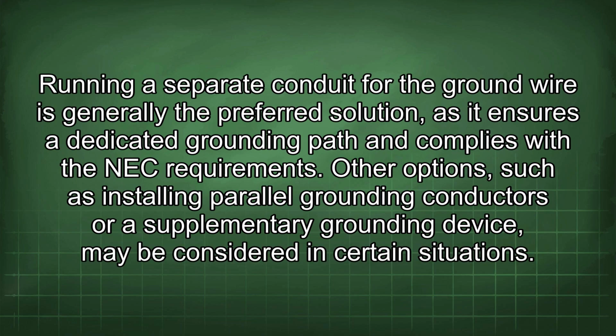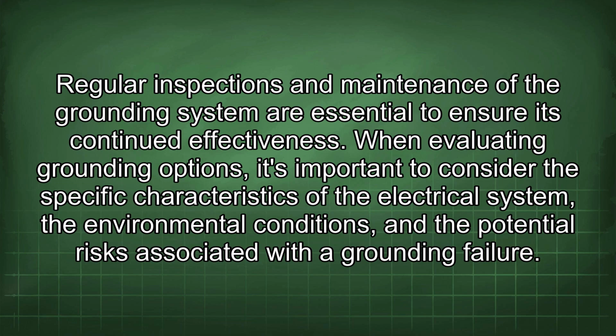Running a separate conduit for the ground wire is generally the preferred solution, as it ensures a dedicated grounding path and complies with the NEC requirement. Other options, such as installing parallel grounding conductors or a supplementary grounding device, may be considered in certain situations. Regular inspections and maintenance of the grounding system are essential to ensure its continued effectiveness.